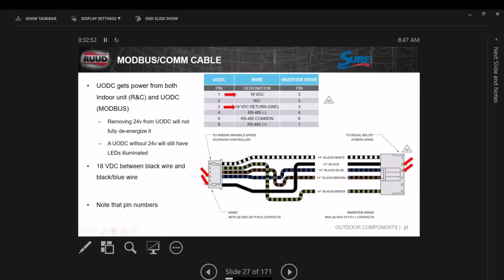But the ones you really have to be most concerned about are number 1 and number 3 on that side, because that's going to be your voltage going and your voltage coming back. If you've got voltage going to a board and nothing coming back, chances are the board it's not coming back from is bad. If you don't have anything going to it, the board's not sending the signals.